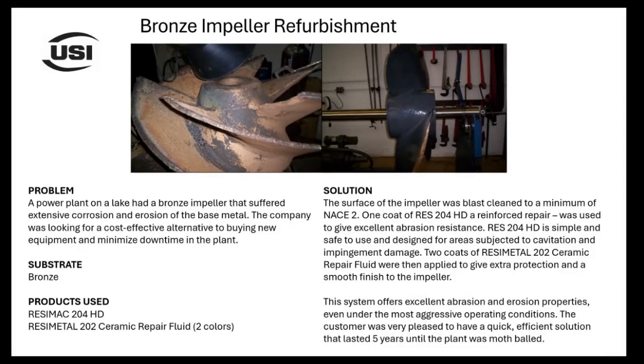The substrate on this one was a bronze impeller. We used our Resimac 204 and 202. According to the TDS, we blast cleaned to a minimum of NACE 2, then applied one coat of Resimac 204 HD as a reinforced repair, which provides excellent abrasion resistance. Resimac 204 is simple and safe to use, designed for areas subjected to cavitation and impingement damage. Then we put two coats of Resimetal 202 ceramic repair fluid on there for extra protection, essentially building it back up with the 204 and using the 202 to create a protective barrier.